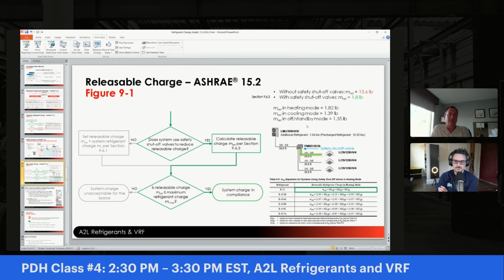In this example, we've got one of our multi-systems, still residential, but with several different indoor units connected to it. These safety valves are built in, like I mentioned. This is a little different — we call it a branch distribution, or BD box, and it'll have a shutoff valve in it as well. In this particular system, without the valves, the total system charge is about 14 pounds, 13.6. With the valves, the releasable charge for this unit is 2 pounds.